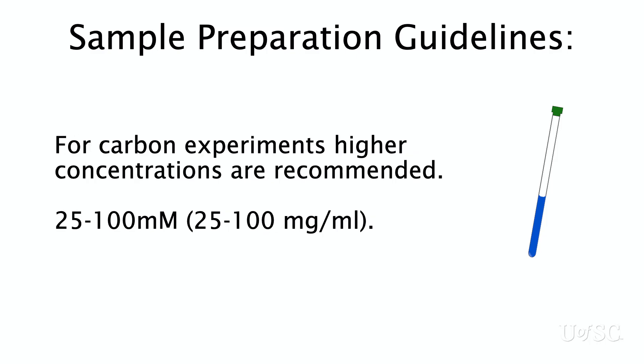For samples that require carbon-13 results, higher concentration will be needed. 25-100mg might be necessary to get a good carbon spectrum with the default parameters, which collects 256 scans over 15 minutes. If you have more dilute samples and need carbon results you should see the staff for your options.